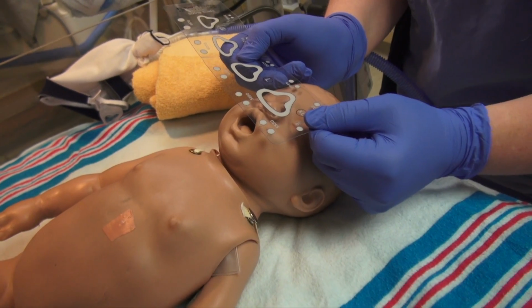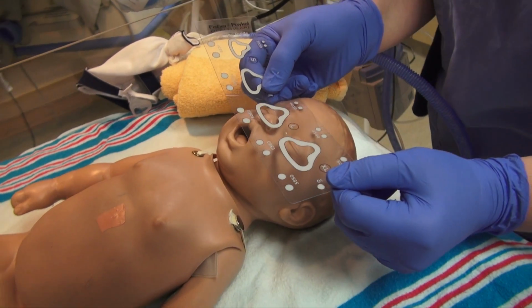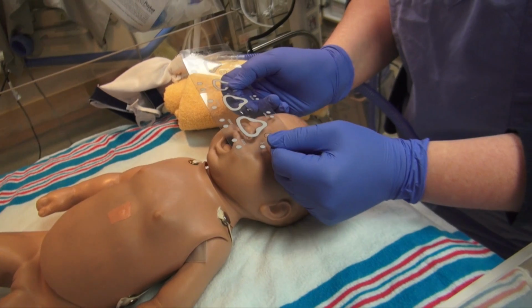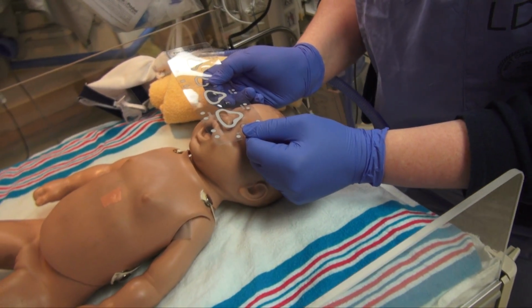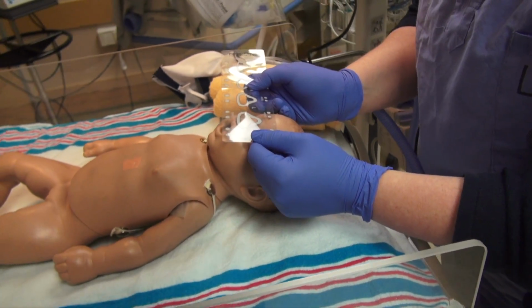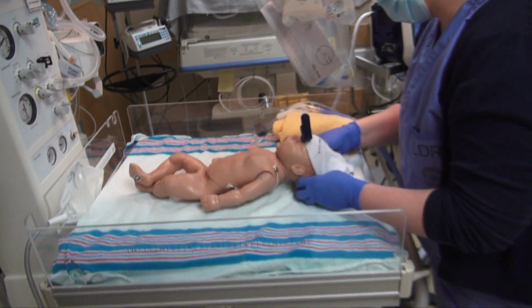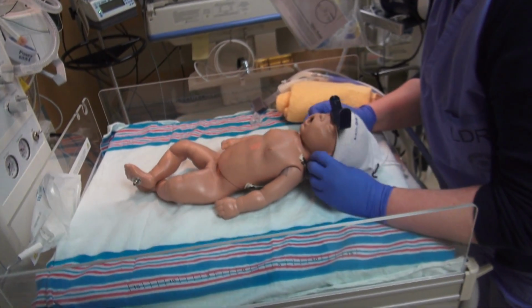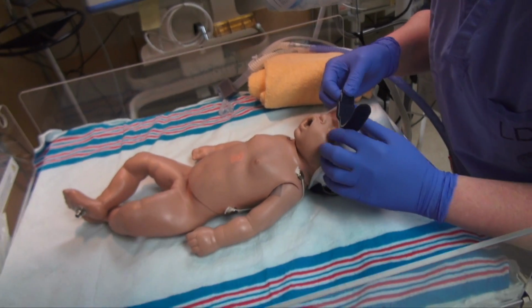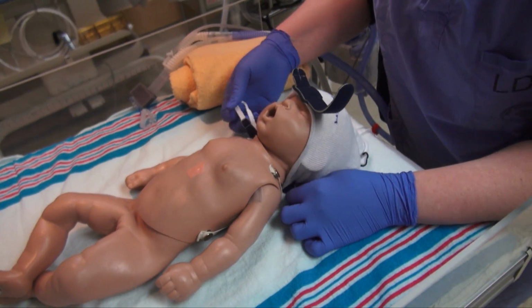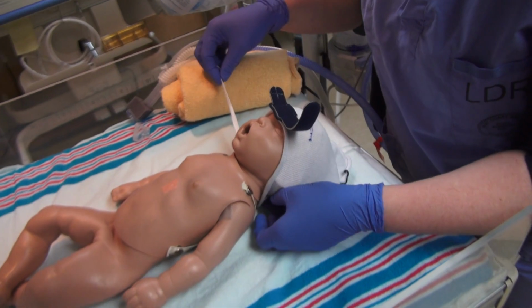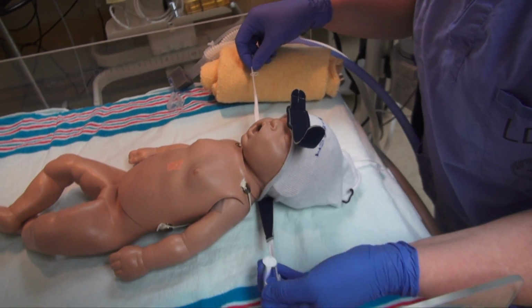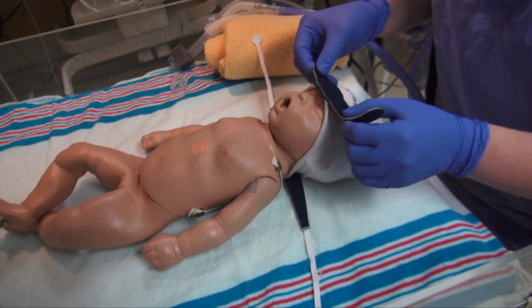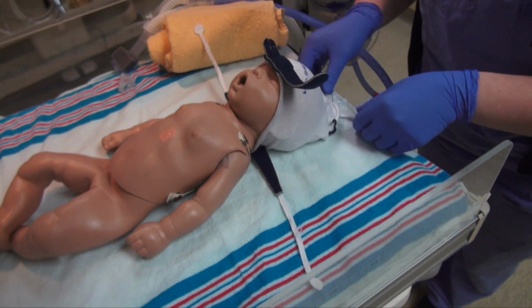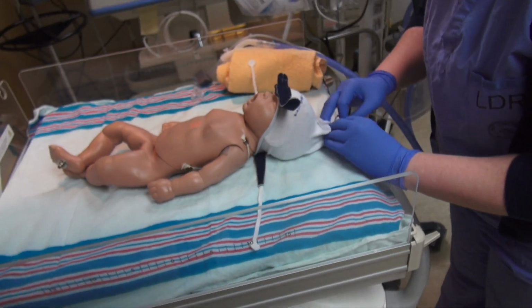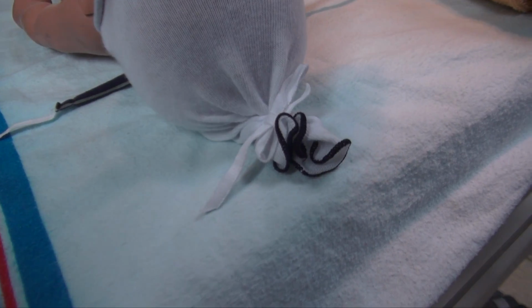Use the sizing guide to choose suitable prongs or mask. The mask should not touch the edge of the nose, septum, or the eyes. Measure the infant's head circumference in centimeters. Choose the correct size bonnet. The bonnet should be snug fitting. Slip the bonnet onto the infant's head, completely covering the ears and with the back edge of the bonnet at the base of the neck. The front edge of the bonnet should be just above or on the eyebrows.